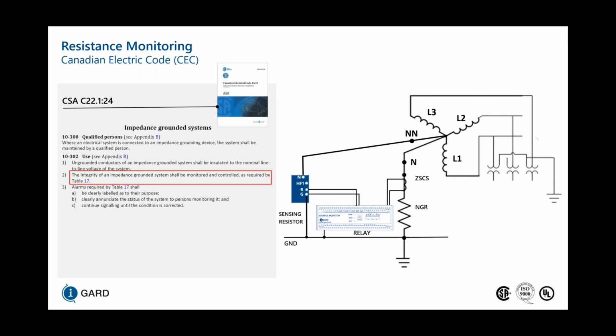So we already had the sensing resistor in play to monitor for open circuit, and we were using a known voltage and known current at the neutral to pick up resistance faults. And we were also using a DC based injection method at the time that we were initially just looking for open circuits. But when 2018's Canadian Electrical Code came around, there was a change in monitoring for both open and short circuit, and we realized that we needed to adjust our methodology from a DC based injection to a high frequency AC based injection.